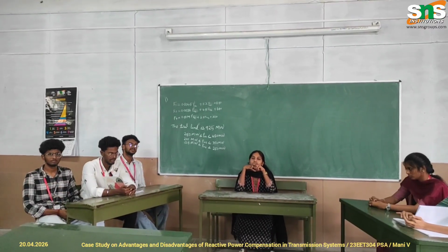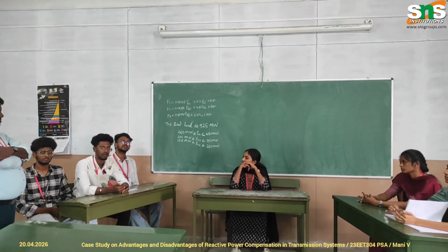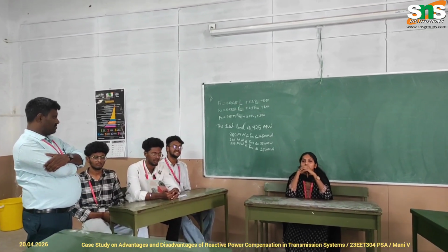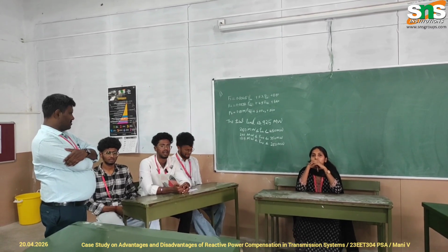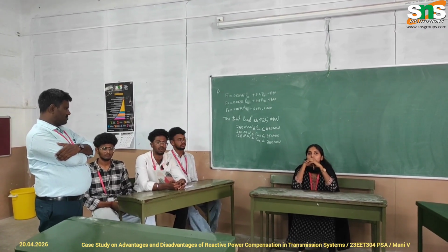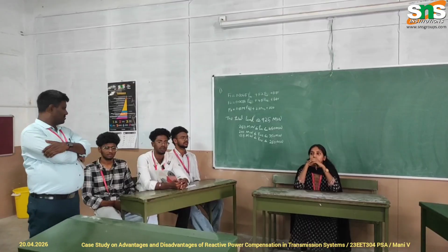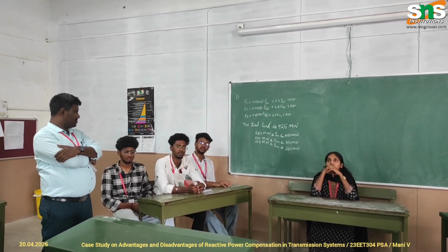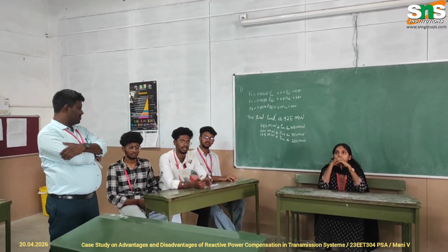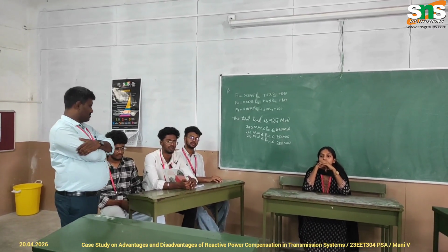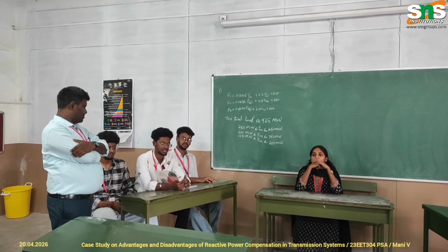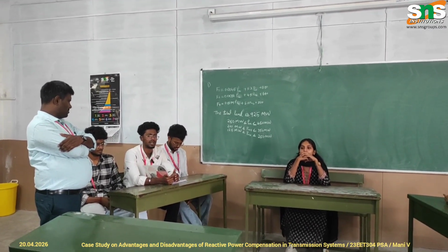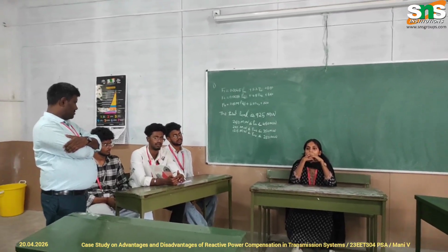Tell about the focus of system stability and dynamics. Advantages: enhanced dynamic stability. Compensation devices like STATCOMs can be used to identify voltage grid faults and rectify them within a millisecond, helping the system remain synchronized after a disturbance. The main disadvantage of these STATCOM devices is that they can introduce harmonics into the system, which requires adding a filter.